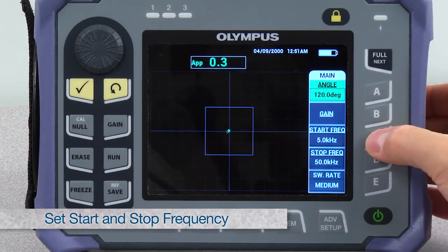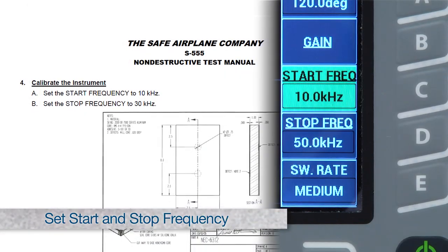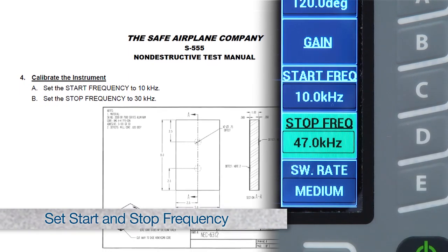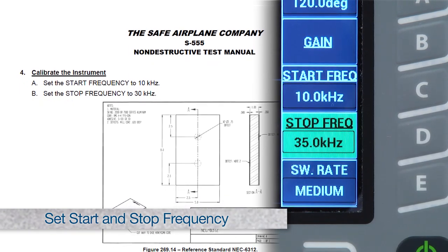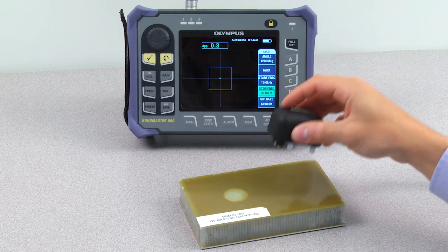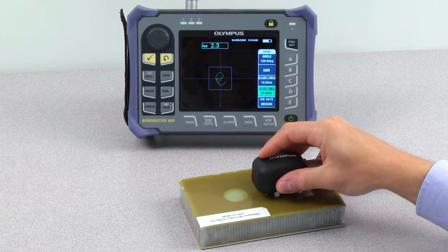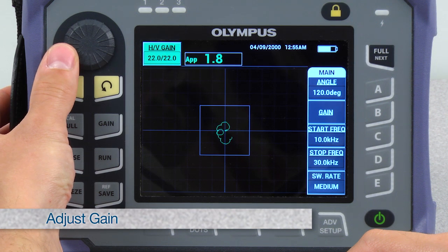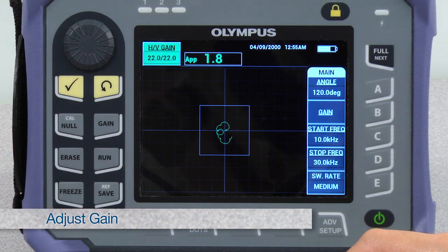If desired, change the start frequency and the stop frequency as recommended by the part manufacturer or the procedure. Put the probe on the defect-free area of the reference standard and press the gain key. Adjust the gain to maintain the signals within the alarm box.